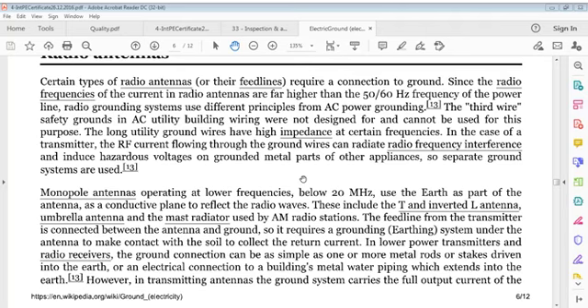Certain types of radio antennas require a connection to ground. Since radio frequencies of current in radio antennas are far higher than the 50 or 60 Hz frequency of the power line, radio grounding systems use different principles from AC power grounding. Third wire safety grounds in AC utility building wiring were not designed for and cannot be used for this purpose.